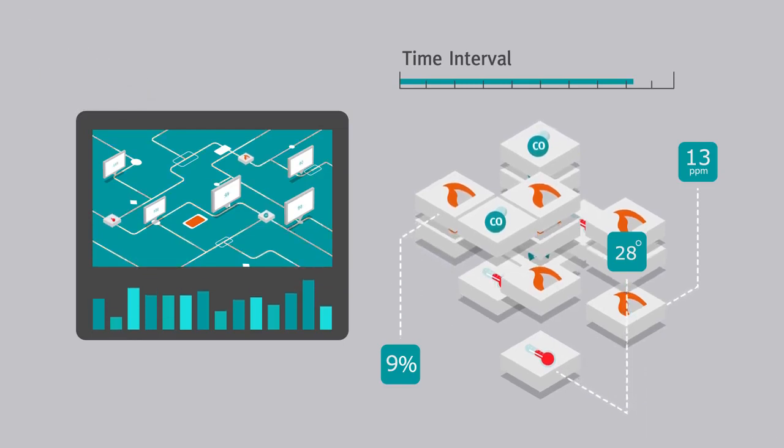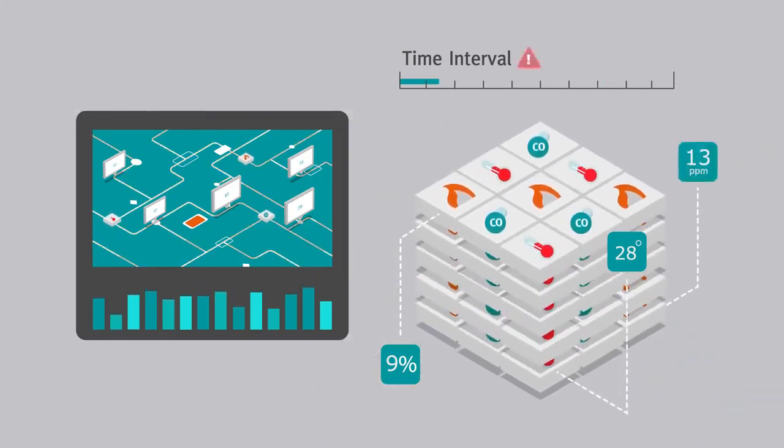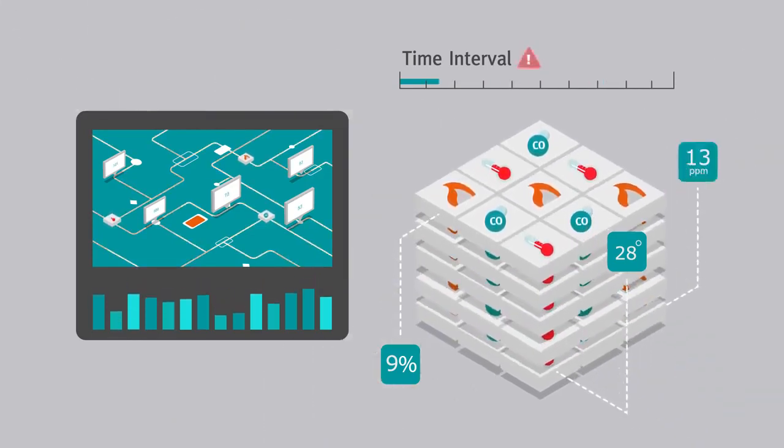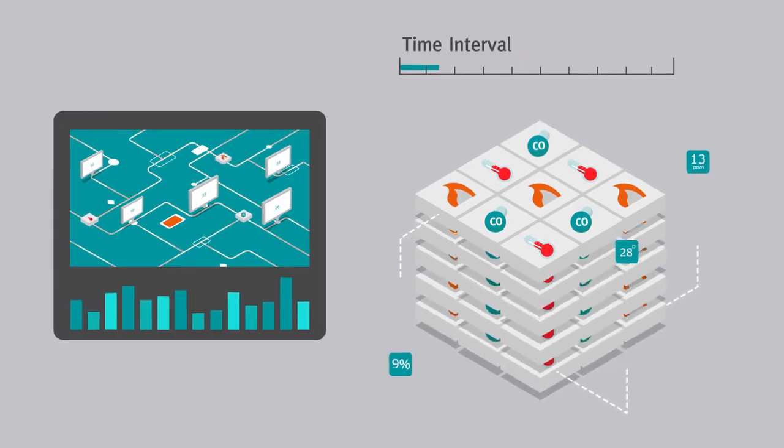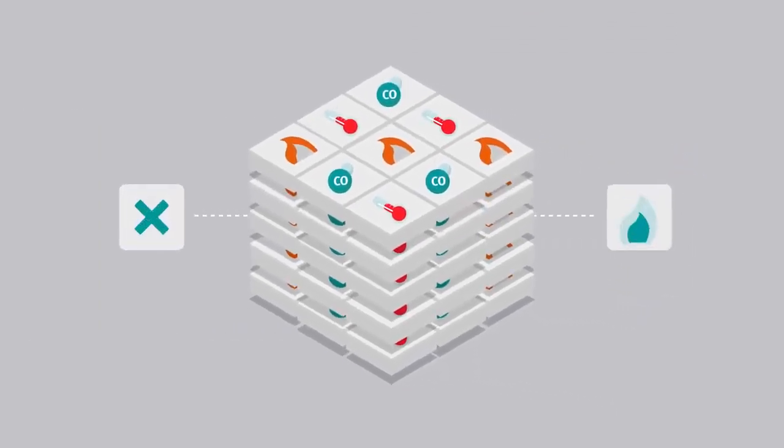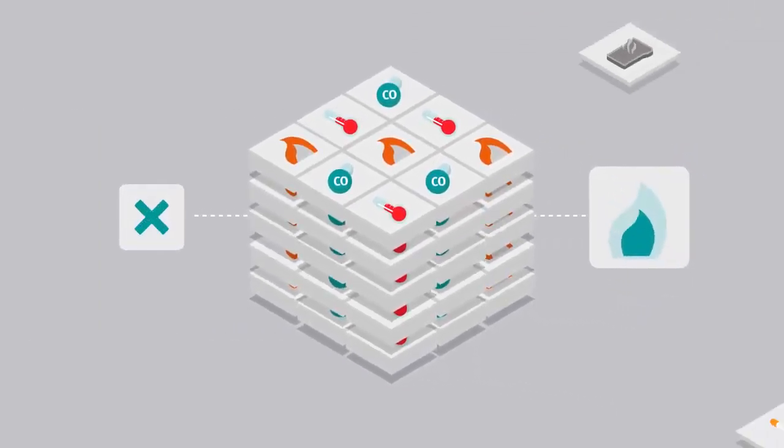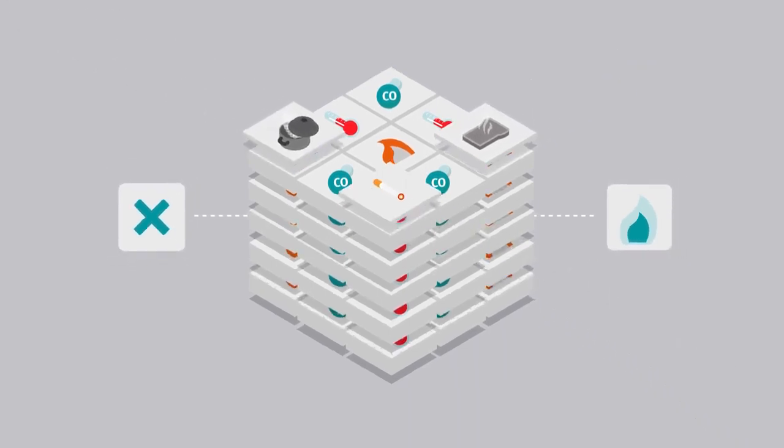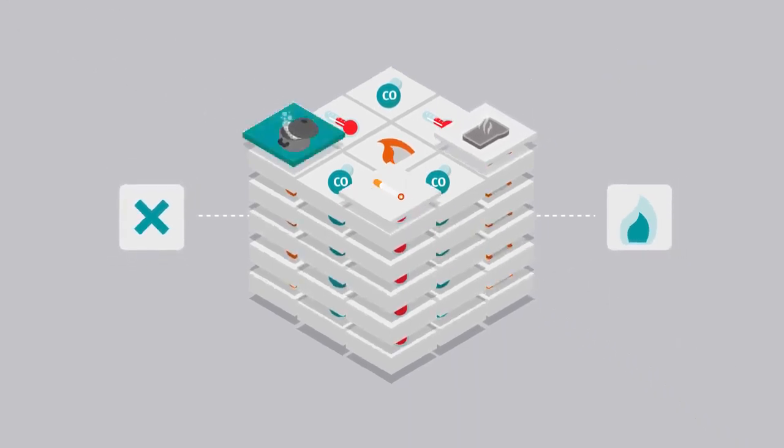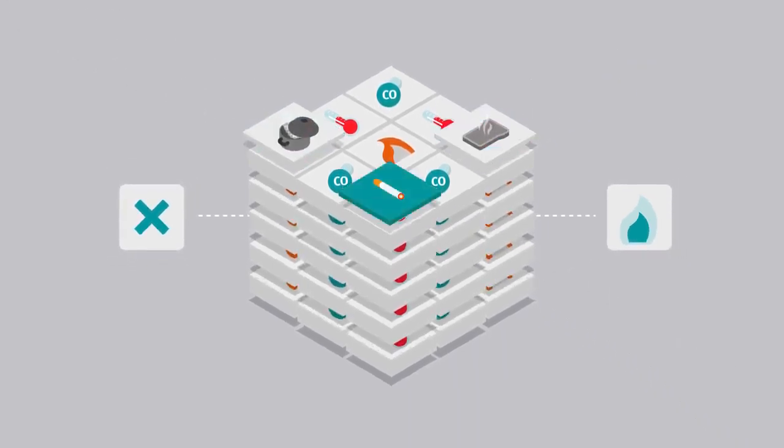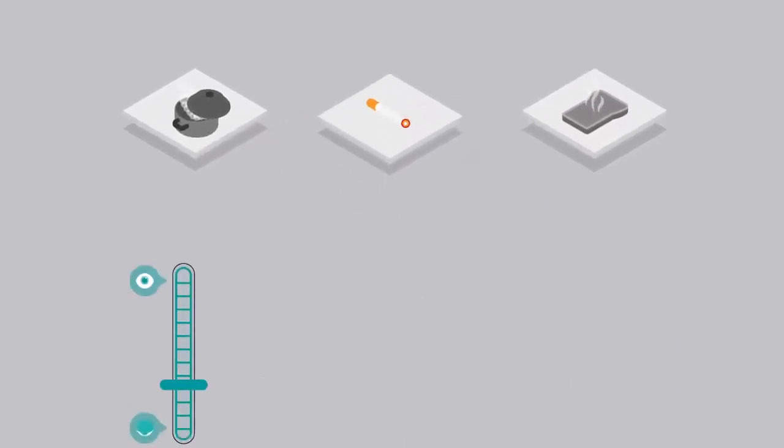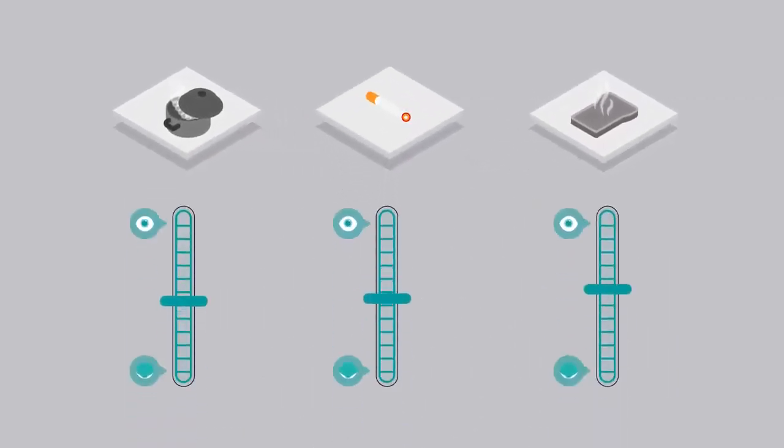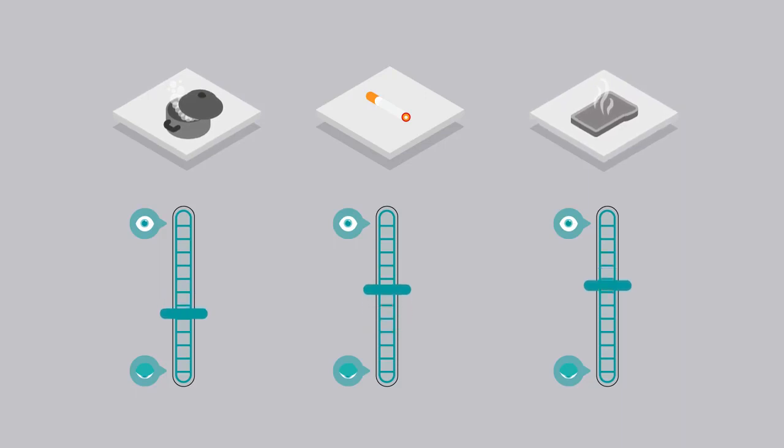However, any transient activity will result in the sensor automatically switching to the maximum number of samples to quickly determine whether the transient is the start of a real fire or a false alarm, such as steam, burning food, or cigarette smoke. In this way, the sensor remains as sensitive as it needs to be based on its environment.